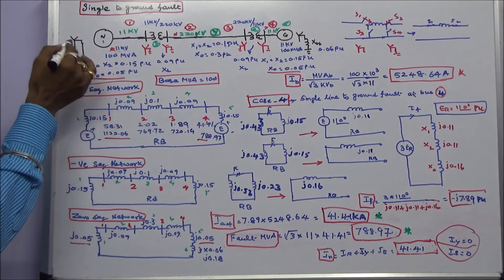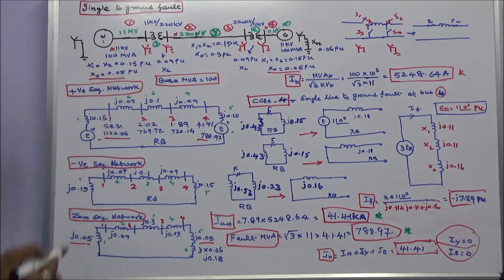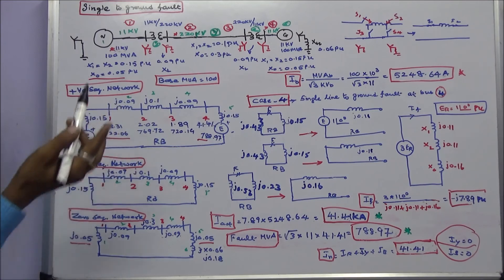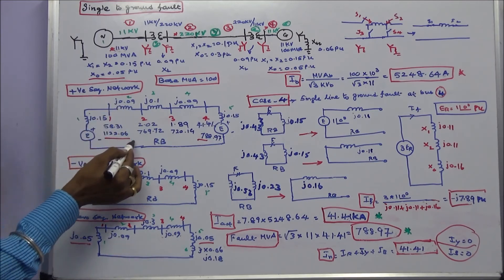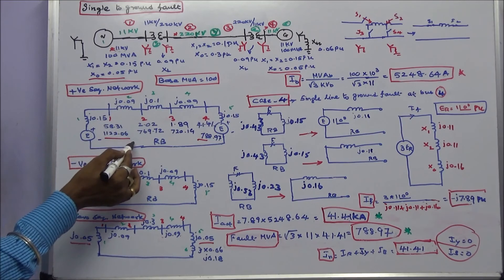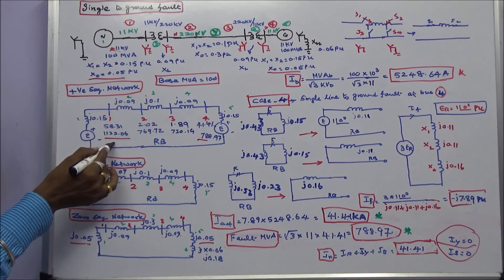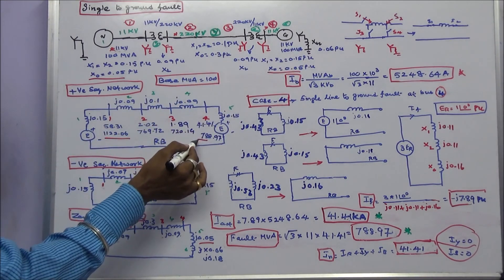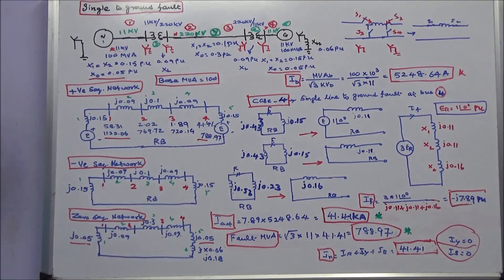This is simply ground and neutral. There is no reactance between neutral and earth. In that condition, fault current is 58.31 kilo amps and fault MVA is 1133.06. There is no reactance, so the current is very high and fault MVA is also very high. When we add reactance, the current is reduced and fault MVA is also reduced. With this I conclude my lecture. Thanks for listening.